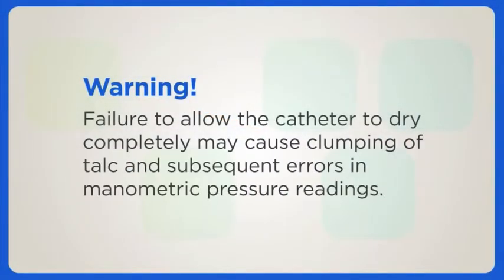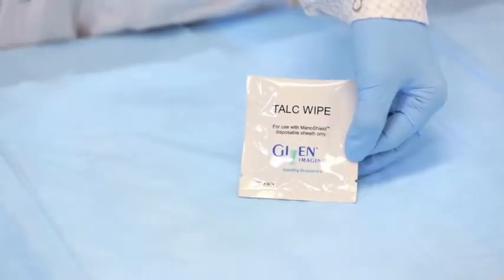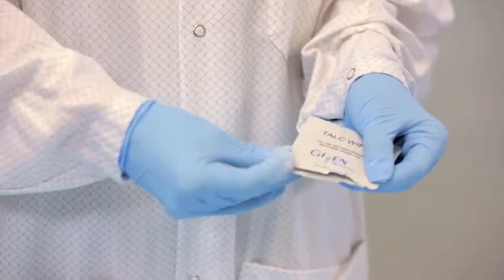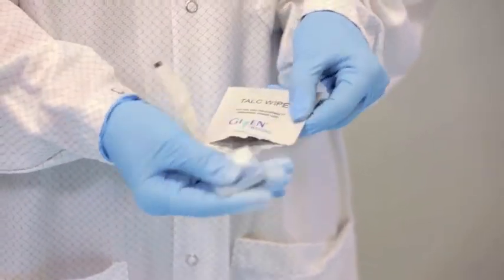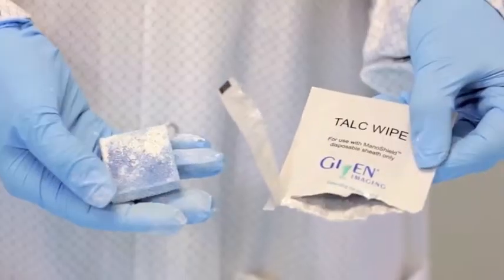Warning: failure to allow the catheter to dry completely may cause clumping of talc and subsequent errors in the manometric pressure readings. A thin, even coating of the supplied talc lubricates the catheter surface and facilitates application and removal of the ManoShield from the catheter.